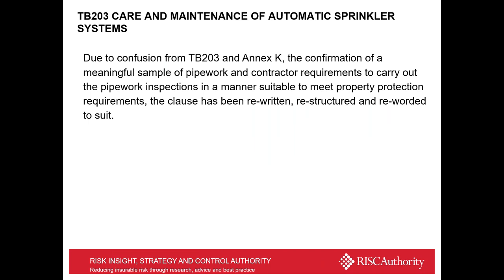Moving on, TB203, pipework and Annex K. The insurance industry are struggling at this moment with poor reporting, with little or no evidence confirming that pipework has been inspected. We've also witnessed this in sprinkler reporting when we've done our independent inspections for systems over 25 years, and deterioration of pipework. So we have now modified TB203 and updated it in relation to Annex K, which confirms what a meaningful sample of pipework is.